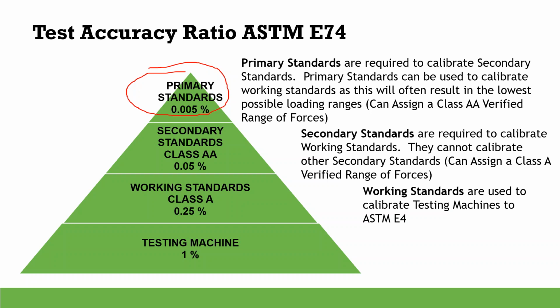So basically what it says, primary standards are 0.005, 50 parts per million. Then secondary standards, guess what? 0.05. That's a 10 to 1. So look what we're building here. We're building an accuracy ratio. Then secondary standards are used to calibrate working standards. Look at that, 0.05 to 0.25. That's a 5 to 1. See what they're doing here? Pretty ingenious. Then these standards are used to calibrate a testing machine, which gives us, I'm writing with my mouse so it's a bit sloppy, a 4 to 1. Look what they've done in this standard. Isn't that nice and sneaky?